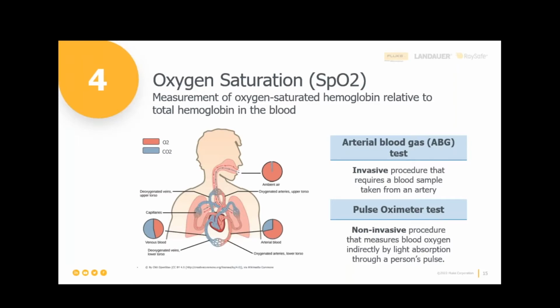SpO2. Let's look at the fundamentals of SpO2. Pulse oximetry uses two wavelengths of light, red and infrared. It needs a pulsatile signal in order to give us a pulse rate. And it's critical to the fundamental measurement, the algorithms that are in place to actually measure the pulse ox, the oxygen saturation level in the hemoglobin.